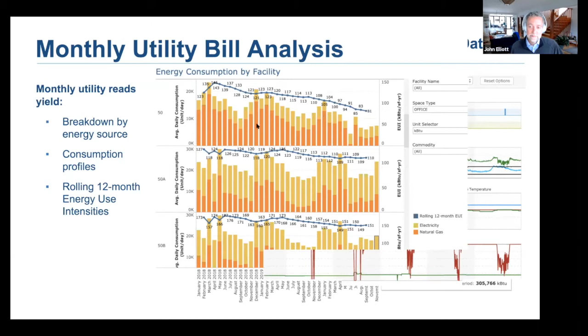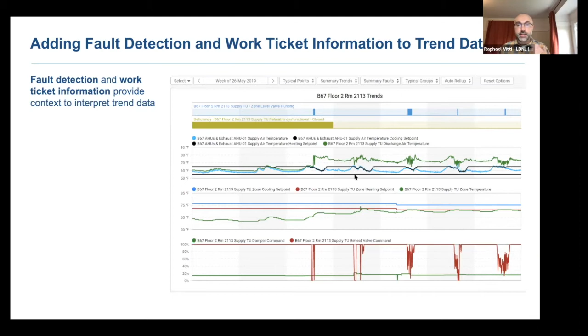This next example is also quite simple, but it's very powerful. What we are doing is showing trending data in context. Here, this specific example is for zone level data. Along with that data, we're displaying relevant trends from the air handling unit that is serving the space, as well as work ticket information at the top and the results of automated fault detection algorithms. That really helps put the data we're looking at into context and helps the operator make sense of it.